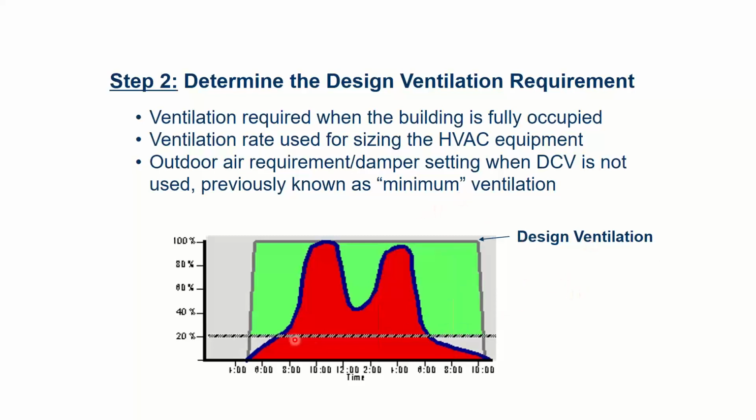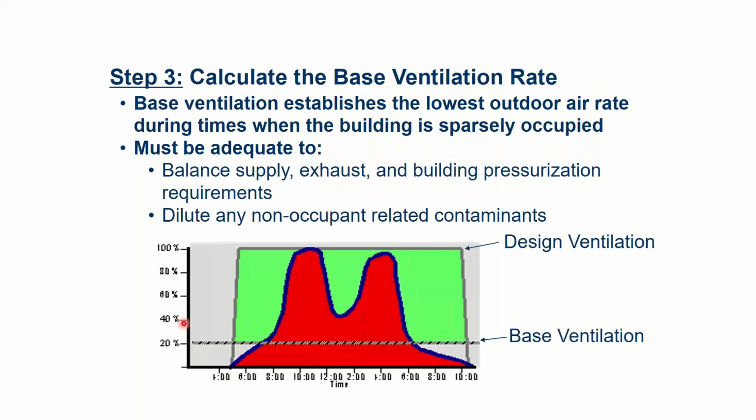I'm going to have to pick some base ventilation rate. I used to have to guess at this. It was totally a guess. And I'd always end up with like 20, 30, 35%, depending on what I was basing it off of, usually pressurization reasons.